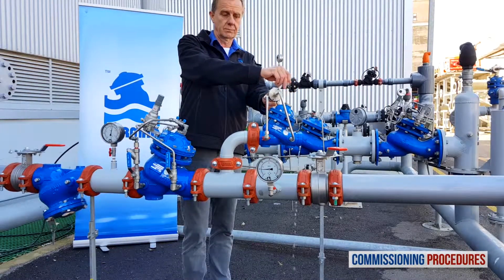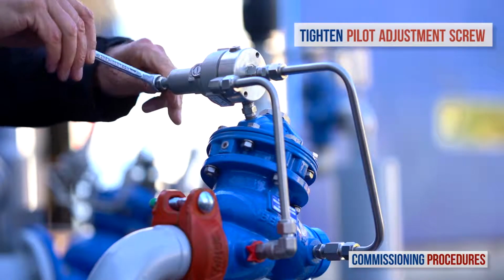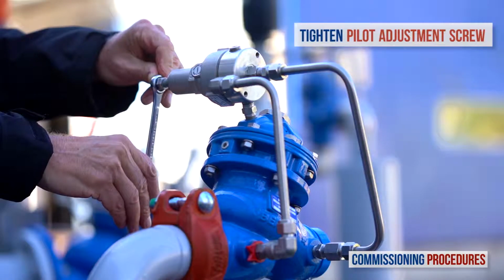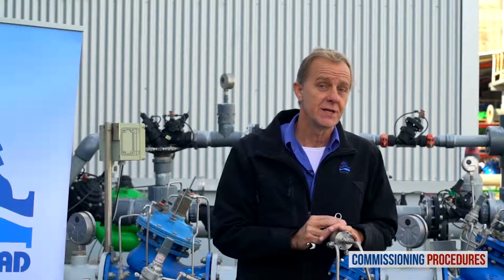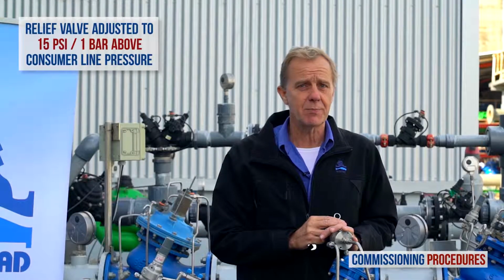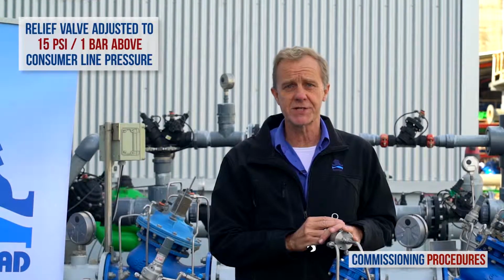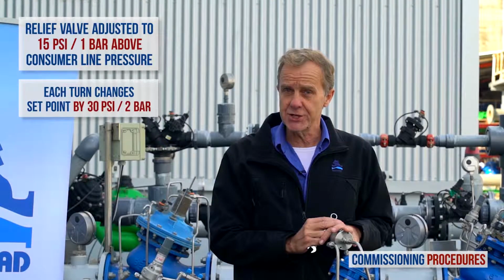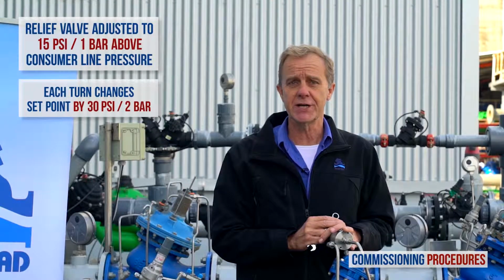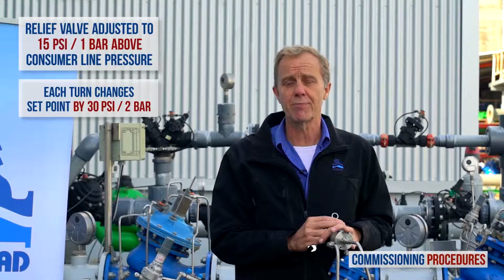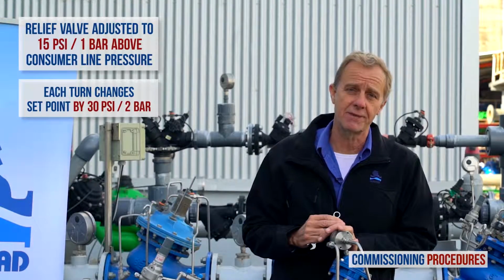Once the leak starts, close the pilot adjustment screw clockwise, 3/4 of a turn. This adjusts the relief valve to a set point approximately 1 bar above the system pressure. Note that each complete turn of the adjusting screw changes the valve's set point pressure by approximately 2 bars or 30 psi.